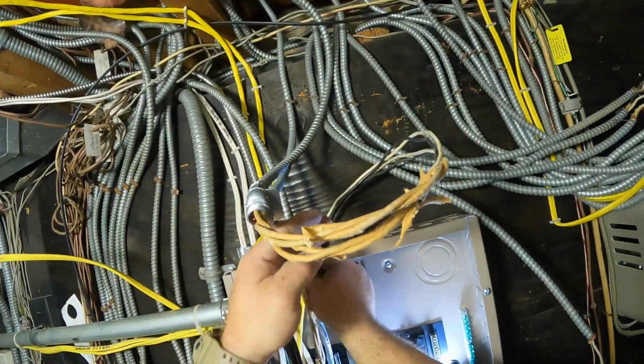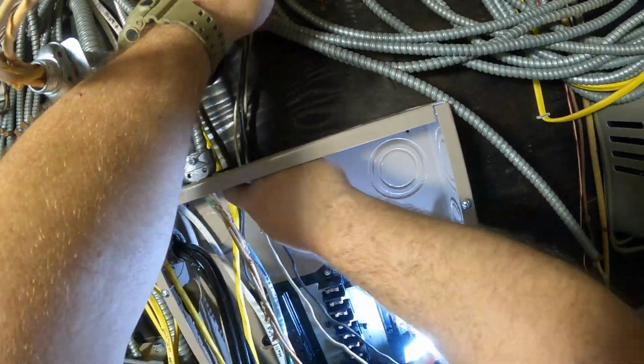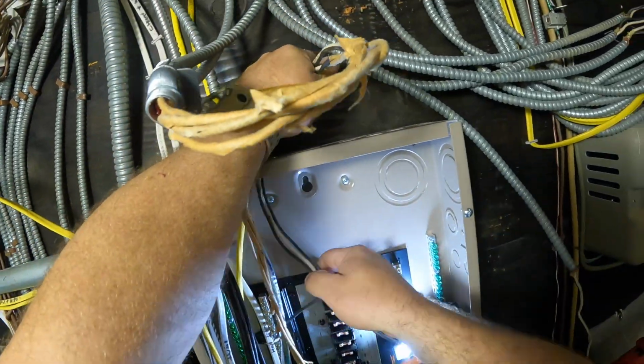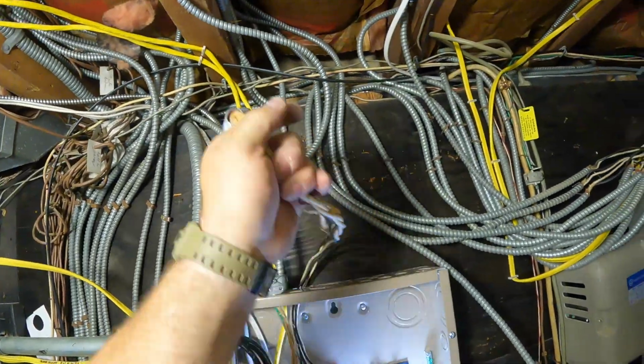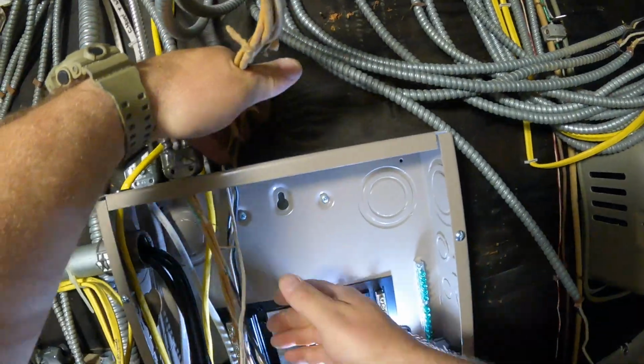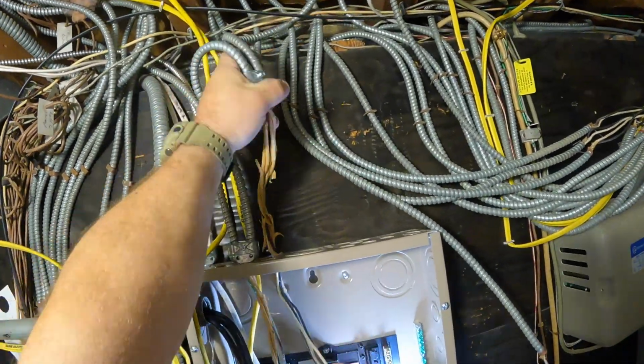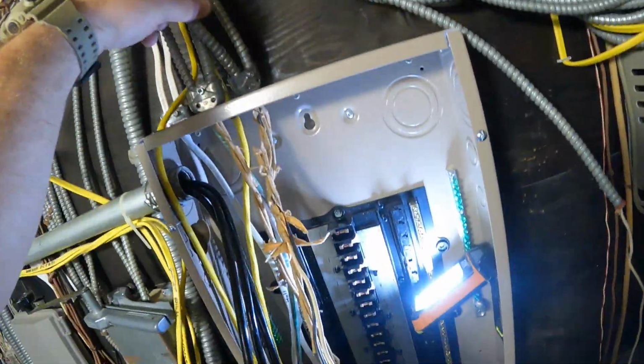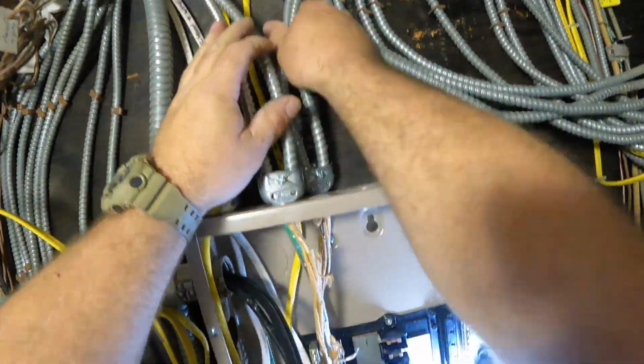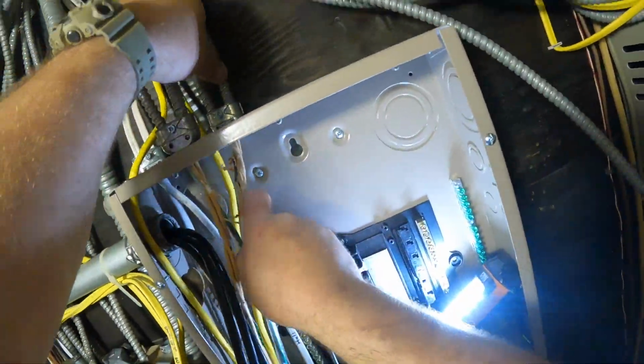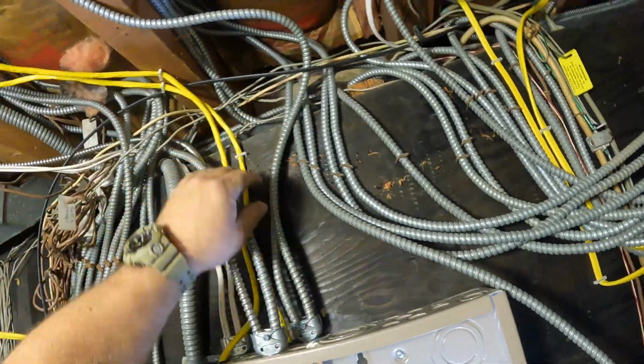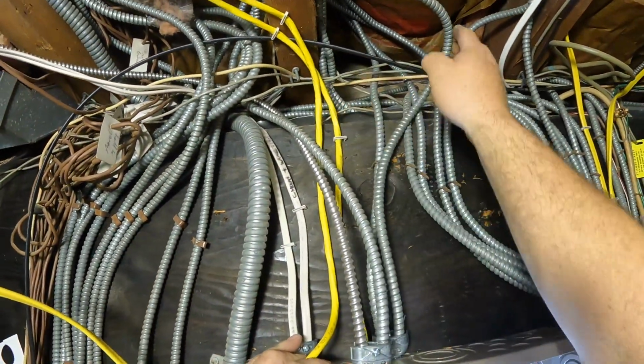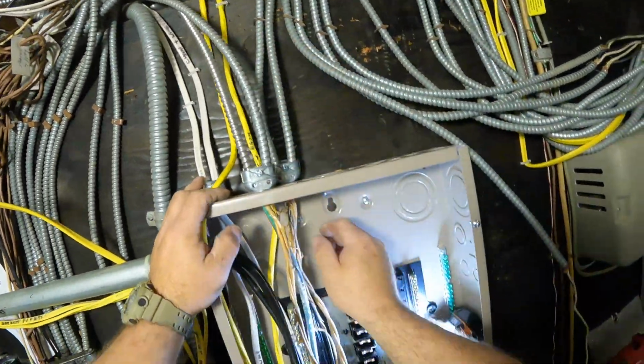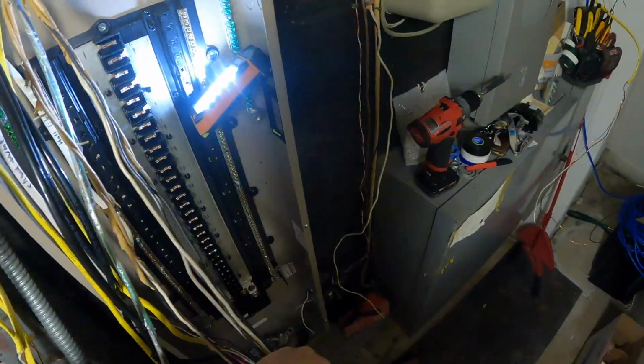Then you can slide your cables and the connector into the enclosure before sliding the lock nut up the wires or the conductors and make a nice tight fit into the enclosure. Now you have two circuits that are properly grounded to the enclosure. This is very, very important. Grounding clears any kind of ground fault. If it's not properly grounded, then you could have a fault and it won't be able to clear itself.